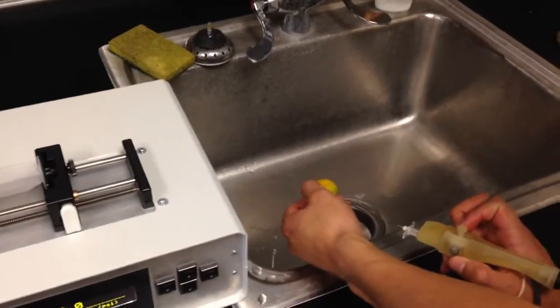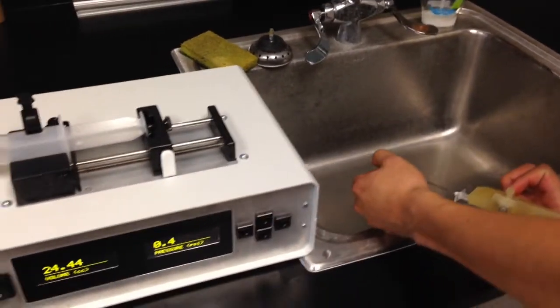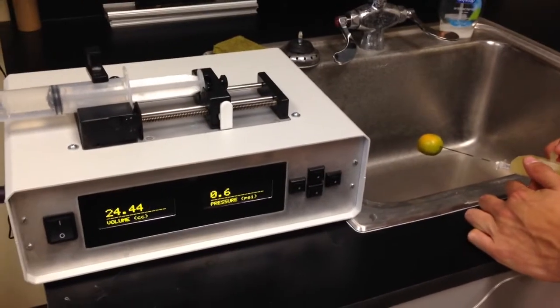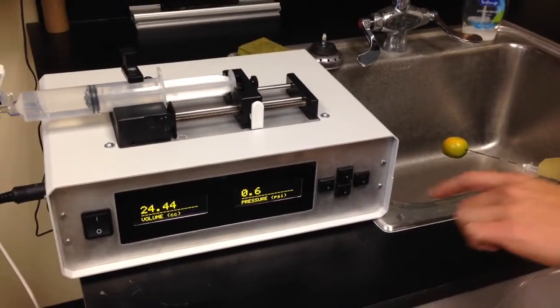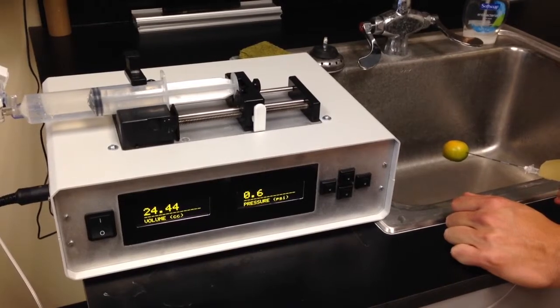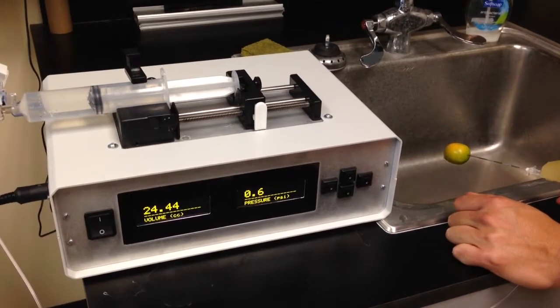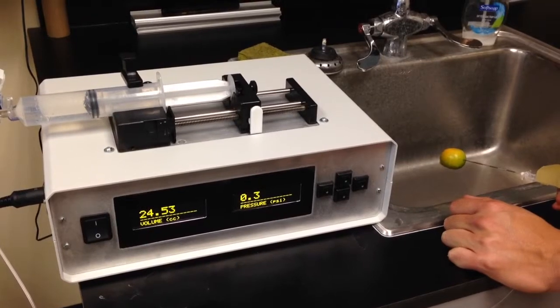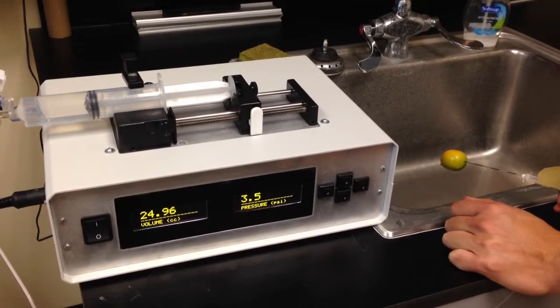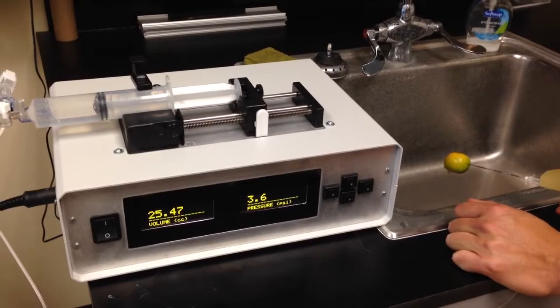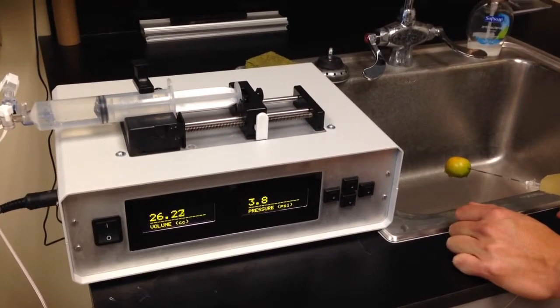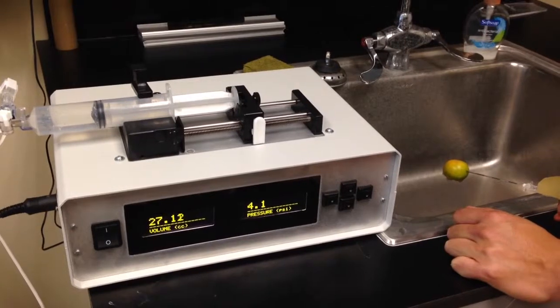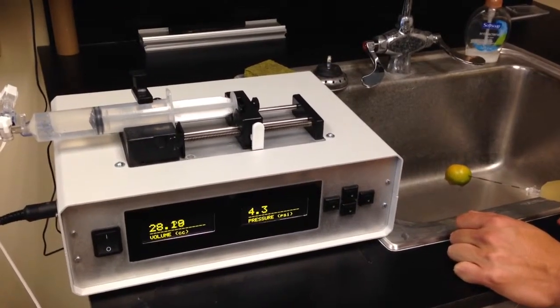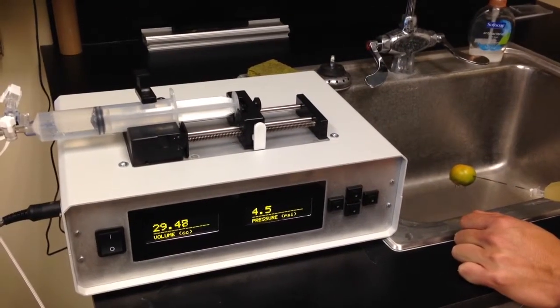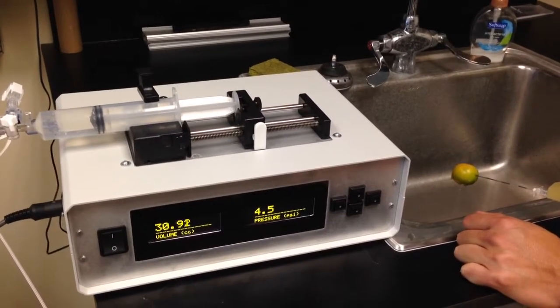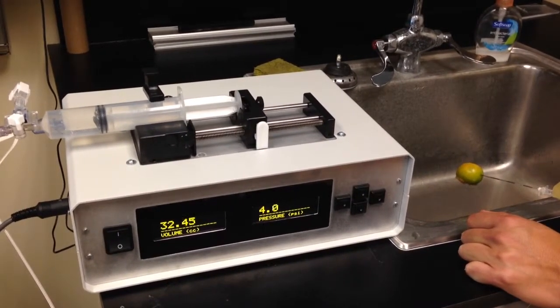So in the same way that you would inject into a subject, the pressure in the body is, as of right now, 0.6 psi, and so he will commence the injection. And because it is a closed body, you see the expected increase in pressure. Some of the fluid is escaping the body as of right now, but for the most part, it is representative of the pressures encountered inside of that fruit.